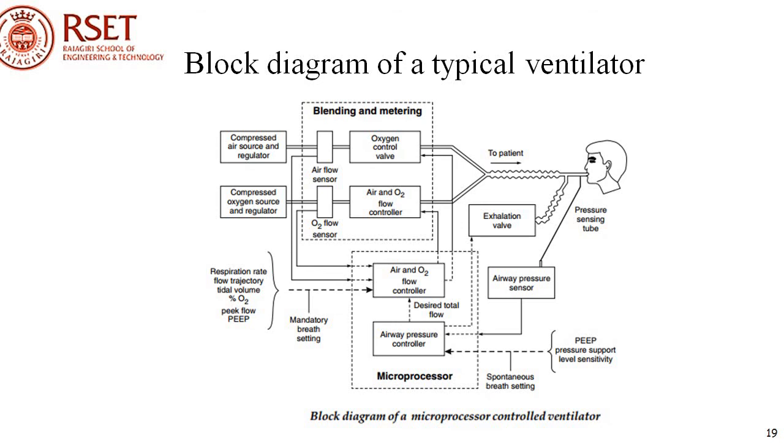It is necessary to provide a time delay between the cycling of the ventilator and the changes from inspiratory flow to expiratory flow in the airway. During this time delay or pause time, the flow becomes zero when the alveolar pressure equals the airway pressure and constant volume is maintained in the lungs.